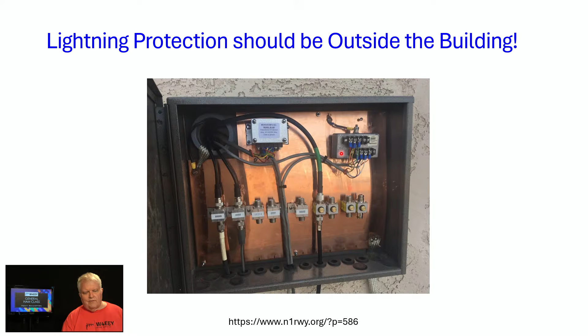Or you can install surge suppressors or lightning arresters, and these should be mounted outside your house or outside the building, and they should be mounted on a copper plate that is grounded, connected to ground wires and rods down below. You can have them for coaxial cable. You can have suppressors for control lines, for rotors and things like that. There's all sorts of different things that are available to you.